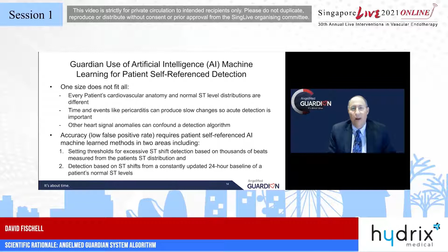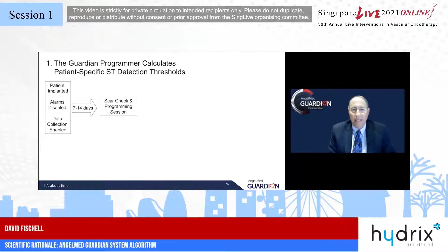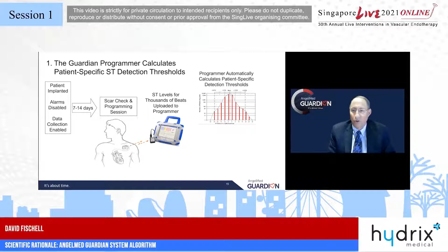Getting each patient's ST change detection thresholds right is critical, as described on this slide. At the time of implant, alarms are disabled, and the IMD begins collecting data, measuring the ST levels on thousands of beats. 7 to 14 days after implant, the patient returns to have the incision scar checked. At that time, data on the collected ST levels for thousands of beats are uploaded to the programmer. These data are analyzed statistically, and thresholds for excessive ST shift are calculated automatically by the programmer, creating thresholds that are typically 3 standard deviations outside of the mean of the patient's normal ST levels, so that normal patient activity will not trigger detection. The programmer is then used to download these thresholds back to the IMD, and alarms are enabled.